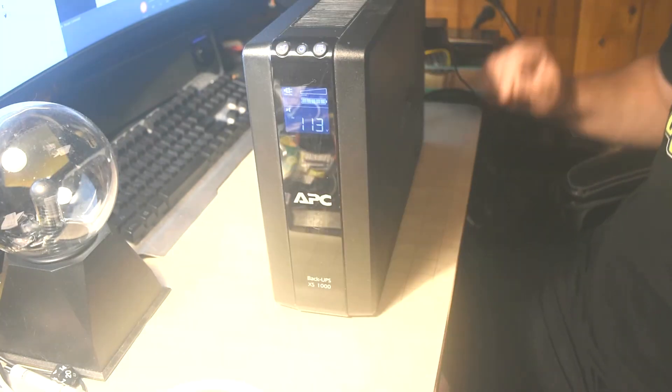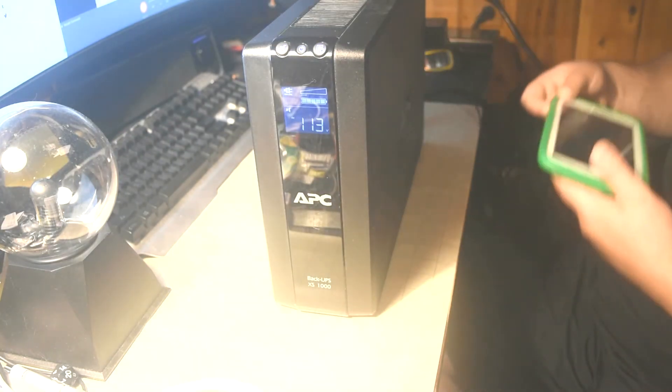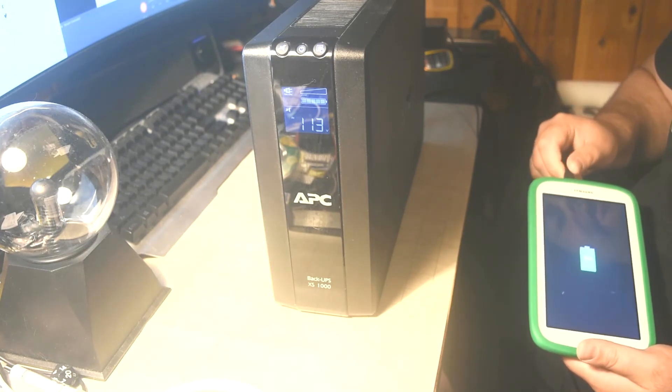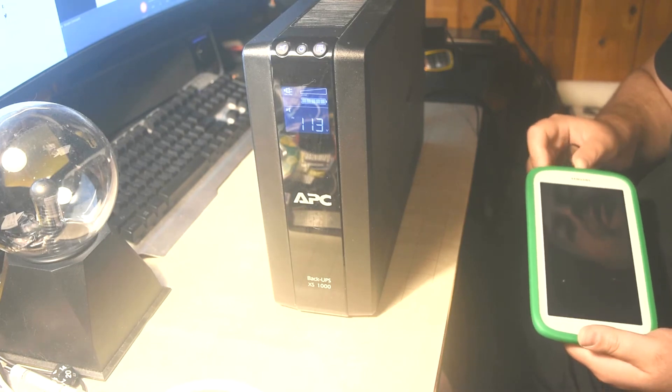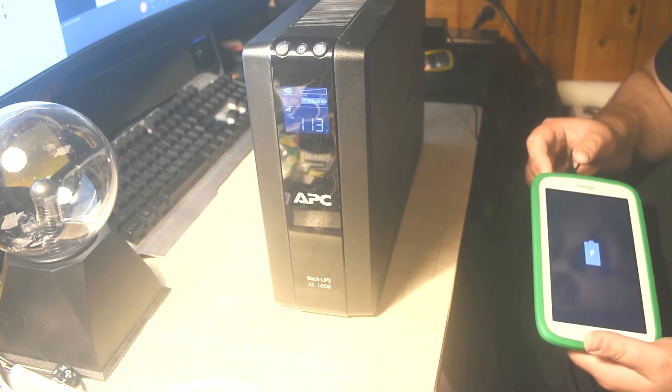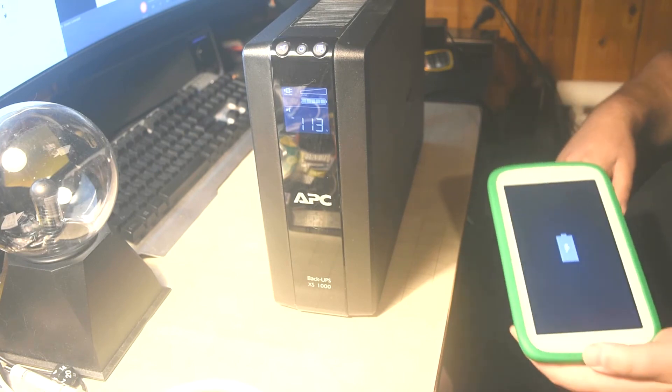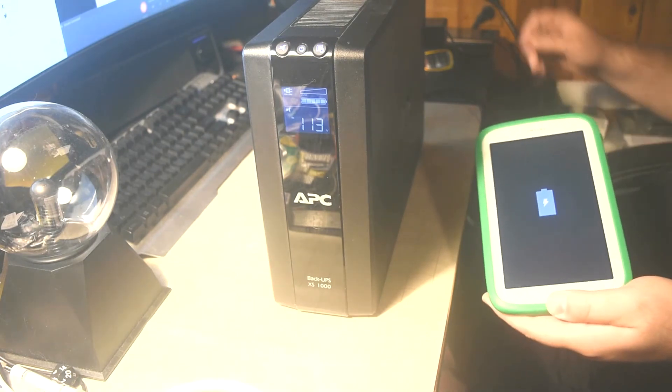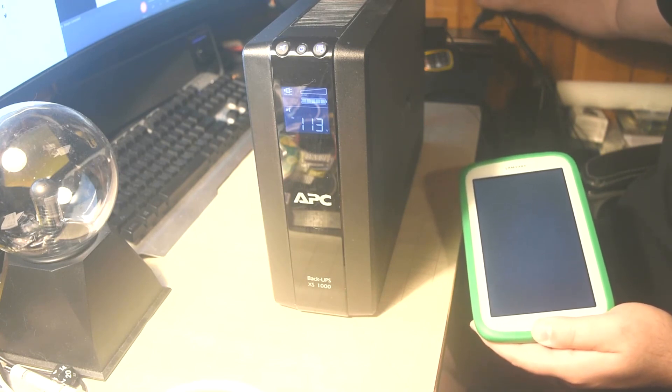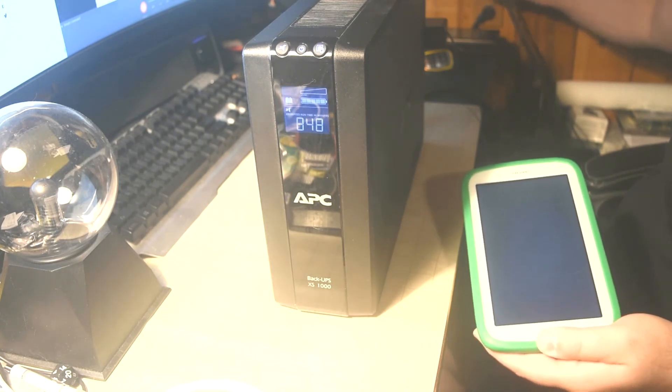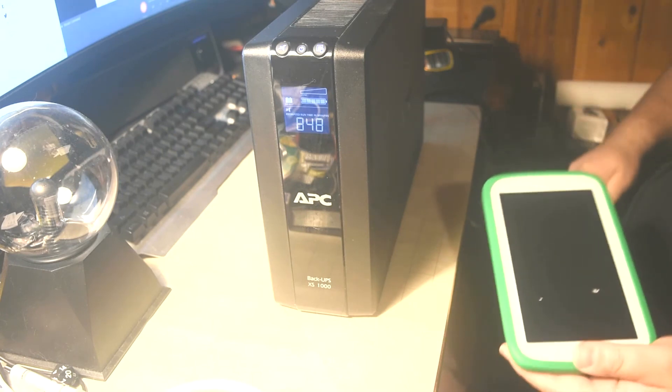The display light is also showing an online status. There's no load registered because obviously there's nothing plugged into it. What is important is, will it still charge even after I've pulled out the unit from the wall? If I pull the unit off the wall and now it's strictly on battery, you see how it switched from online to now it's on battery power.